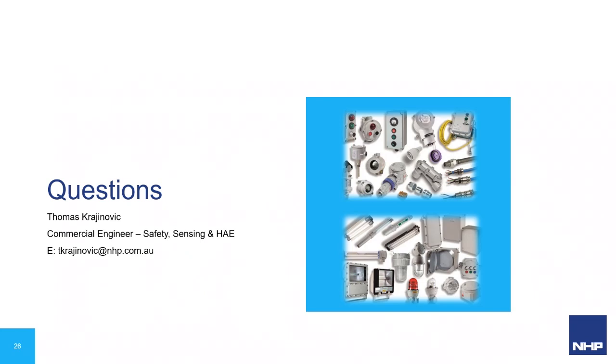So in this case, it'd be 60079.10.1 to cover gas and vapors. And it would have a lot of examples there, especially towards the appendices, which would have pretty much that example that you would be able to find. But you would definitely need to get the environment classified first, and more than likely it would be either a zone 1 or zone 2 environment, and you would need light fittings that are suitable for that zone.